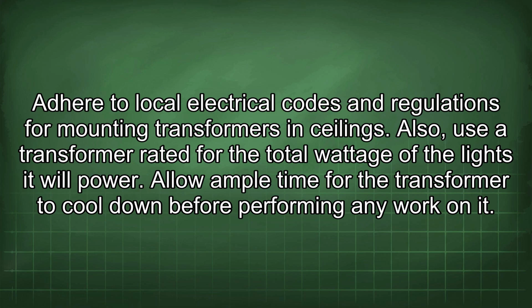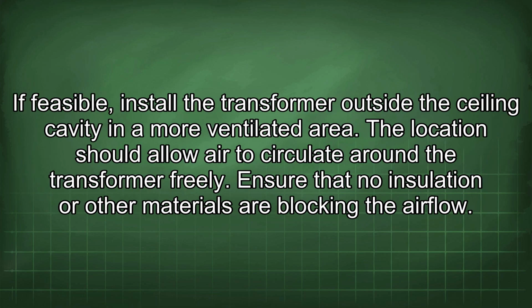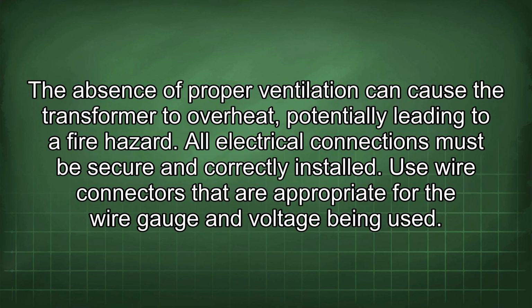Also, use a transformer rated for the total wattage of the lights it will power. Allow ample time for the transformer to cool down before performing any work on it. If feasible, install the transformer outside the ceiling cavity in a more ventilated area. The location should allow air to circulate around the transformer freely. Ensure that no insulation or other materials are blocking the airflow. The absence of proper ventilation can cause the transformer to overheat, potentially leading to a fire hazard.